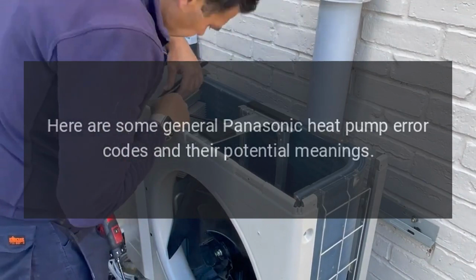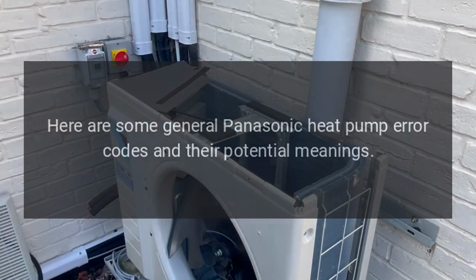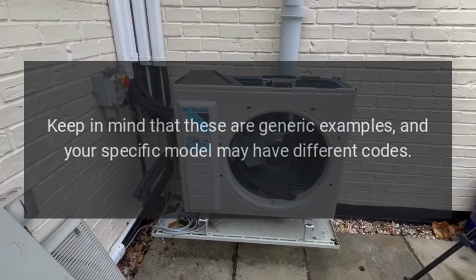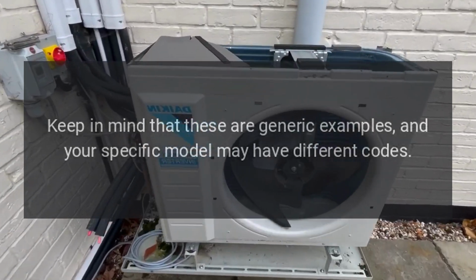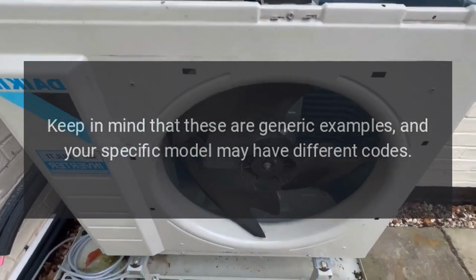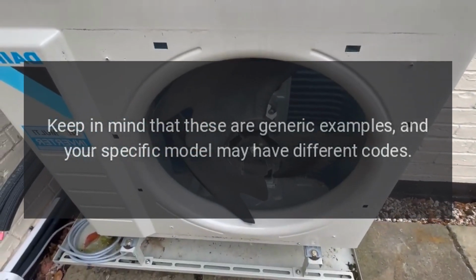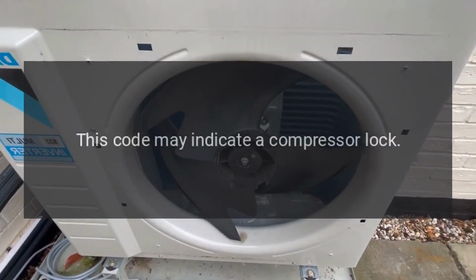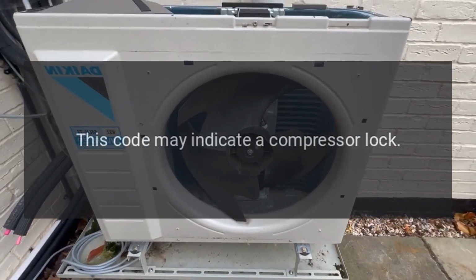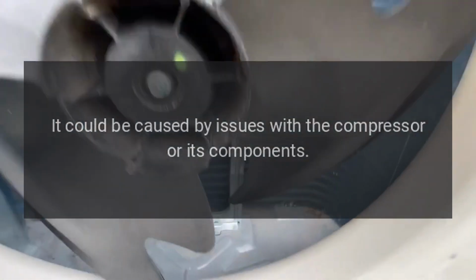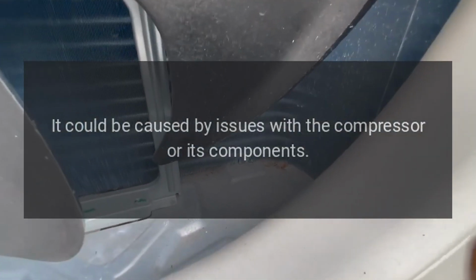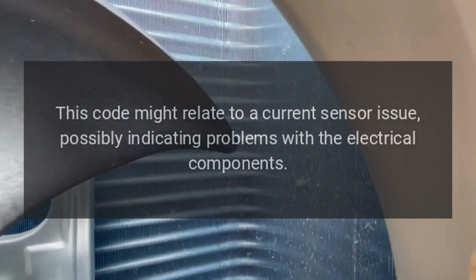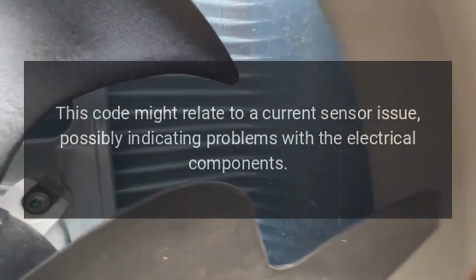Here are some general Panasonic heat pump error codes and their potential meanings. Keep in mind that these are generic examples, and your specific model may have different codes. H11. This code may indicate a compressor lock. It could be caused by issues with the compressor or its components. H12. This code might relate to a current sensor issue, possibly indicating problems with the electrical components.